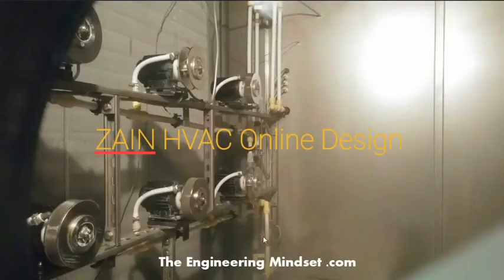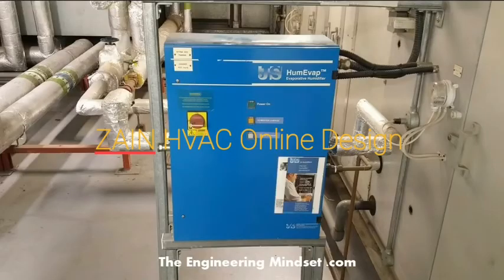So this is a humidifier here, so it's got water coming in and it's just spraying this out. These small induction motors are spraying that water out in a very, very fine mist, and as that sprays out and creates the mist, that goes off, and that's what adds humidity to the air, increases the water content of the air. Another way to do it would be through something like this, which is an evaporative humidifier. You can go for a steam system as well, so there are many ways you can add moisture to the air, and it depends on whether the environment is critical or not.